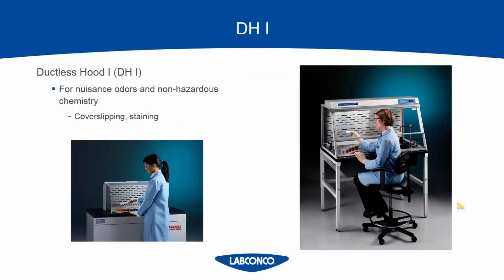So the DH1 hoods are for nuisance vapors. DH stands for ductless hood, and we're going to have 3 different kinds, starting with DH1. These are for nuisance vapors or non-hazardous chemistry. These are typically smaller enclosures and they don't have sensors built into them as a standard item. So the way you tell how to change the filters out, you use your nose, basically. If it starts smelling, then that's when you change the filters out.